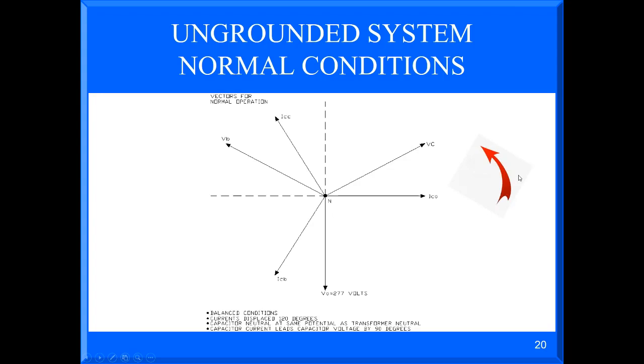While I'm on this slide, the reason I put this arrow on here is I do a lot with metering, also with multi-load. And a lot of customers will say, my power factor shows 0.2. And I know that's wrong. Why is that wrong? It's basically unity, knowing that. No, you should have a lagging, you know, motors. They were saying 0.2 instead of like 0.8 or 0.85. And the reason is their currents and voltage weren't together. I need A phase voltage connected to A phase current, B phase voltage connected to B phase current.